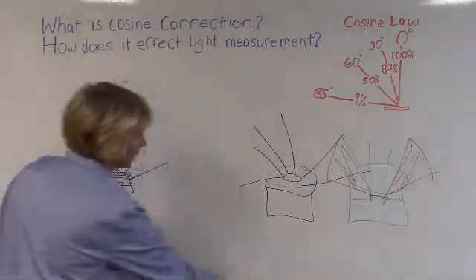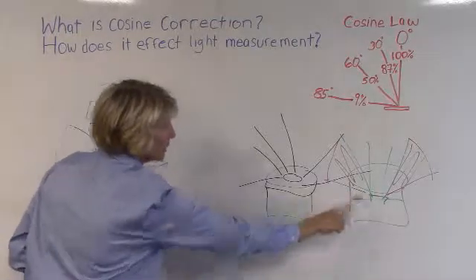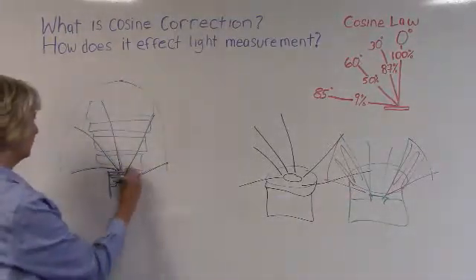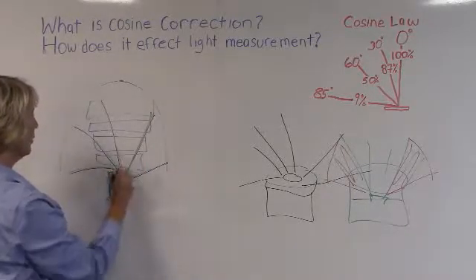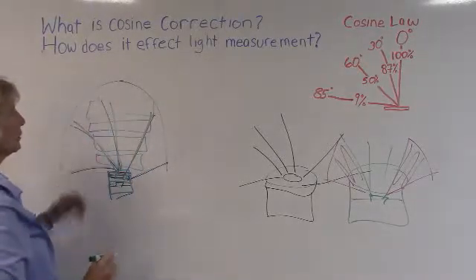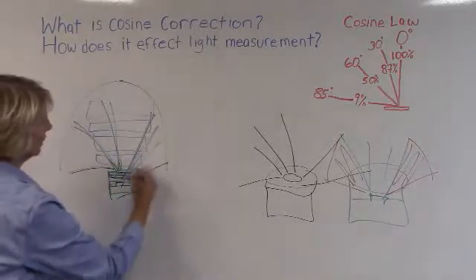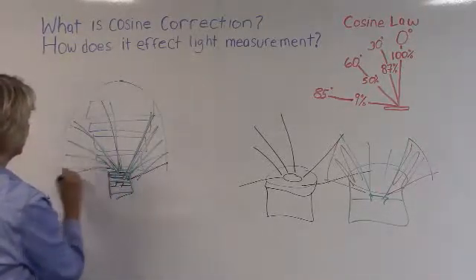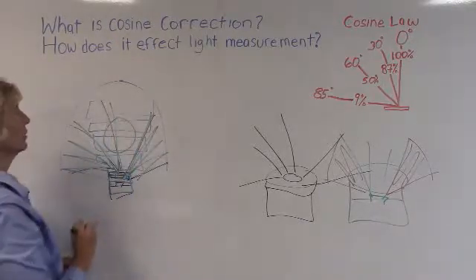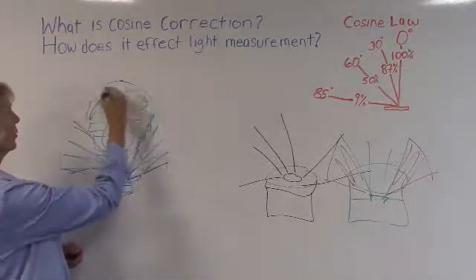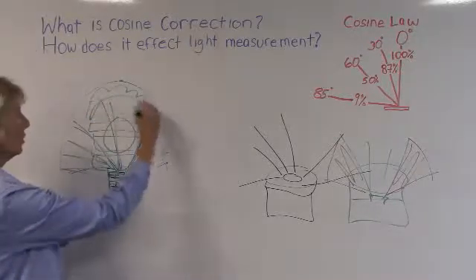However, if you were to take your detector with the recessed housing and no cosine correction, it's going to have a very limited field of view. So this means it's going to miss all of this light. Now if you picture this detector placed underneath all four of your lamps, this could mean that it's missing all of the light from your outer lamps as well as all of the light from the surrounding reflector.